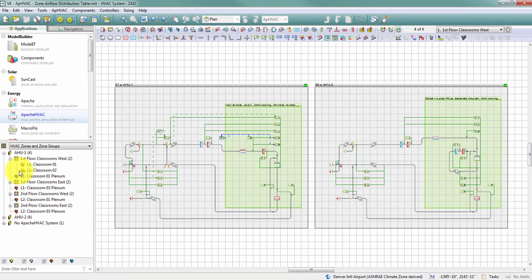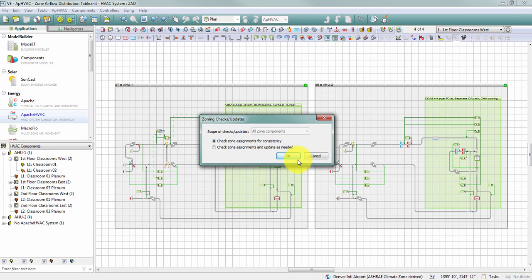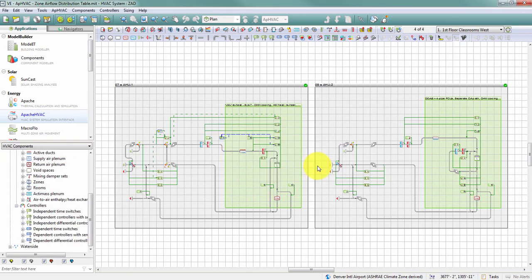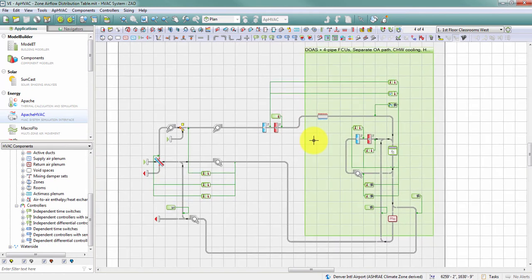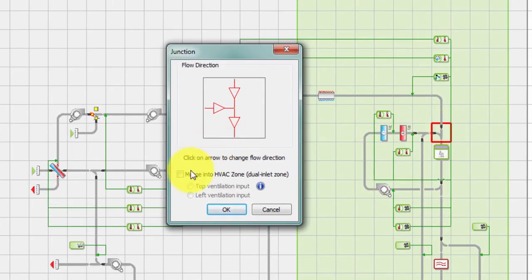Taking a closer look at System 2, I'm switching back to HVAC component mode to make edits. System 2 has a dedicated outside air system and fan coil units. I may want to create a dual inlet zone — to do that, I double-click on the junction upstream of the zone component. In the junction dialog, there's a checkbox to merge into HVAC zone to create a dual inlet zone, with options for a top or left ventilation input.